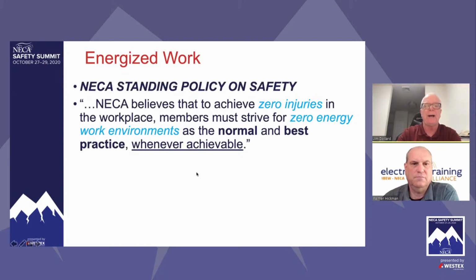As Palmer pointed out, the action to verify de-energization is considered energized work by both NFPA 70E and by OSHA.